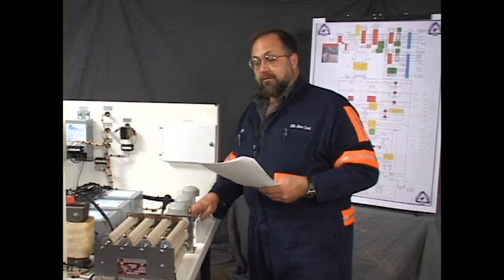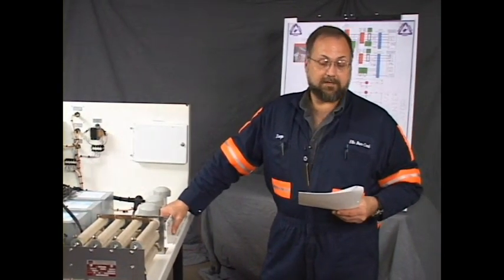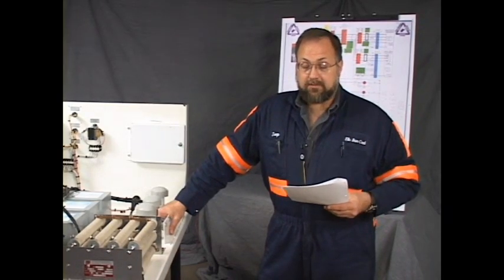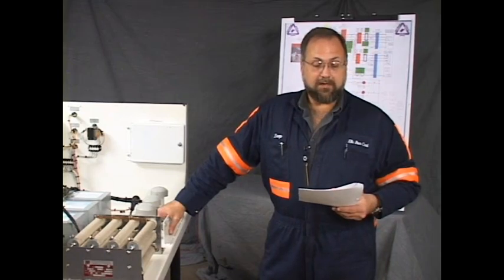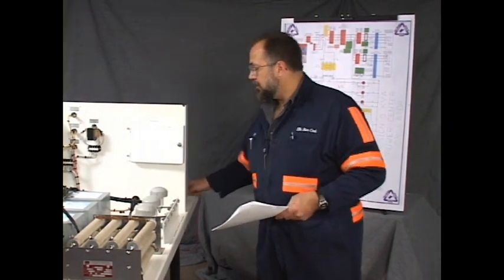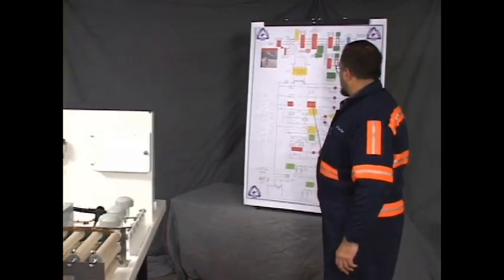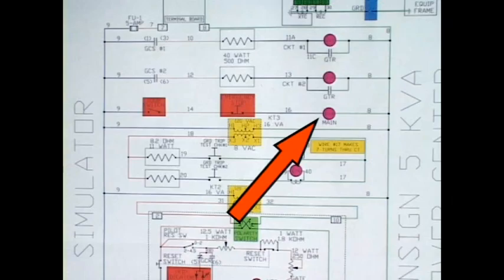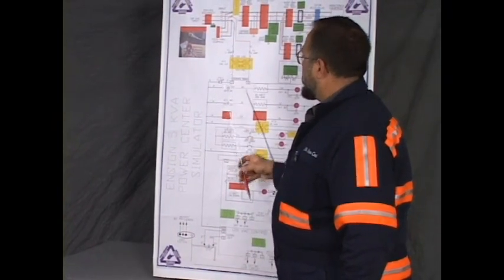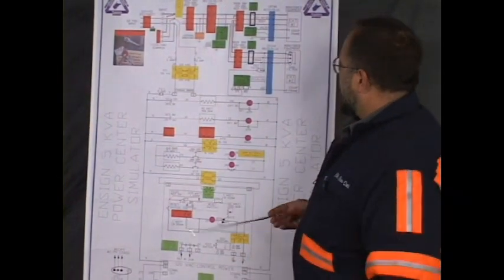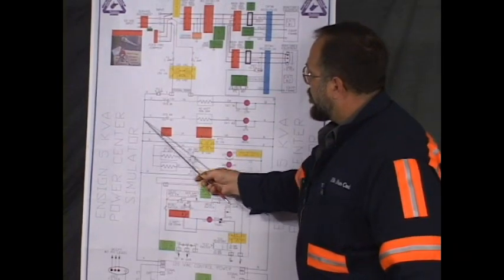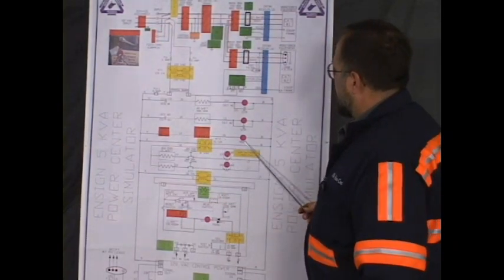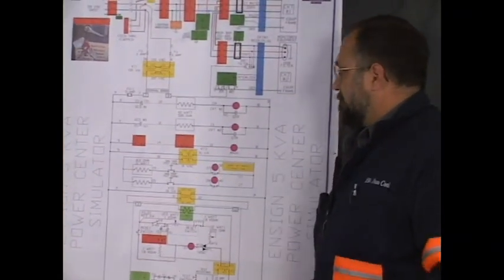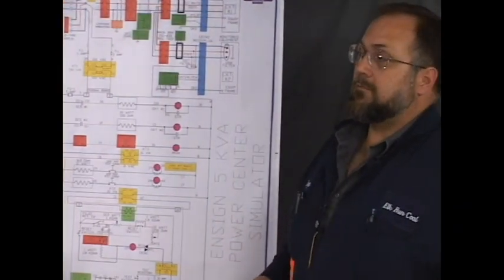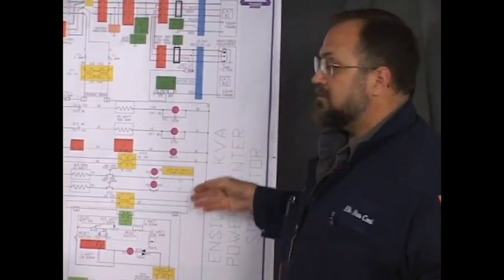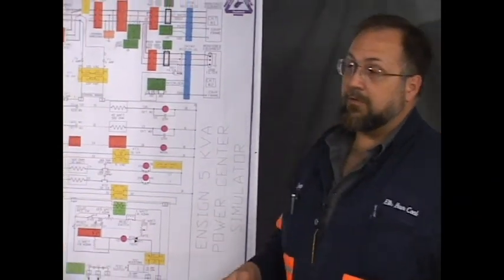It says there's no problem with the breaker, no mechanical problem. It says you have control voltage on the secondary KT1. That's a good place to begin troubleshooting. It says the ESPB contacts are properly closed. There's nothing wrong with the UV coil. The ESPB contacts, they're here. It says the UV coil, there's nothing wrong with it. It says you have control voltage on the secondary, but this breaker won't close. In order for this breaker to close, we need to have a circuit through this line here to the UVR and then back. None of the problems in the simulation are going to be found on the common or the return side of the circuit. And that won't necessarily be true in your real life problems.